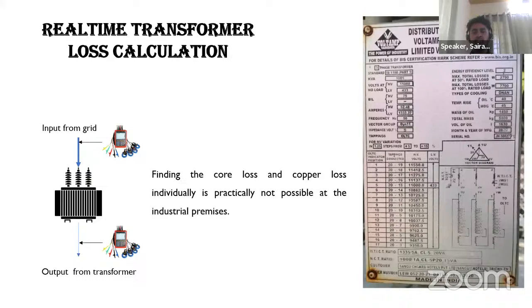If they insist on finding the core loss and copper loss separately, then when a shutdown happens, they have to shut down all the loads and the transformer has to be free from loading. Then we follow the same procedure. The energy consumed by the transformer will be considered as the core loss, and at the time of normal loading condition, we again do the same procedure. If we take the difference between the normal condition and the zero load condition, we will get the core loss and copper loss separately. But it is not practically possible all the time.